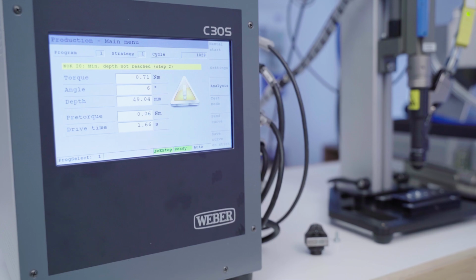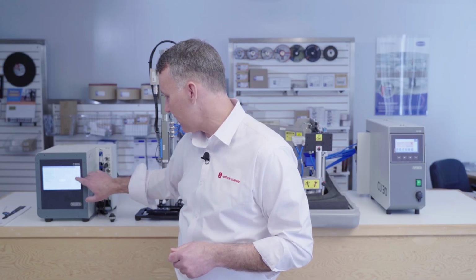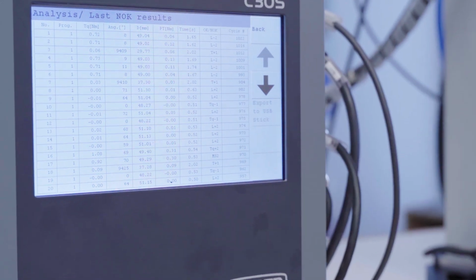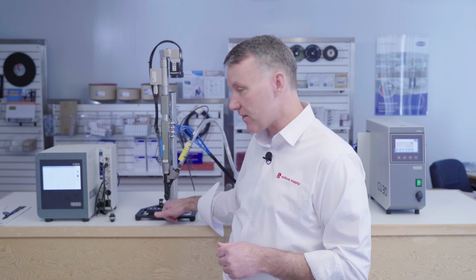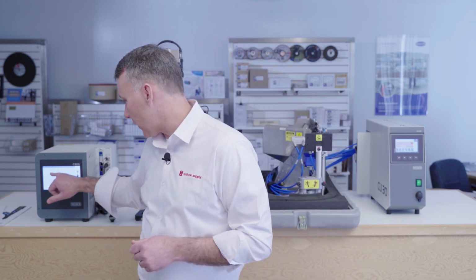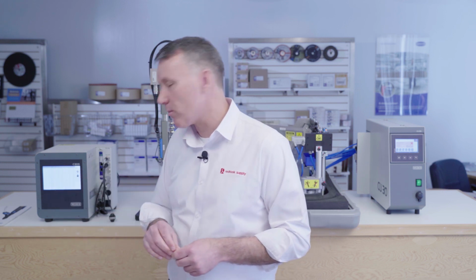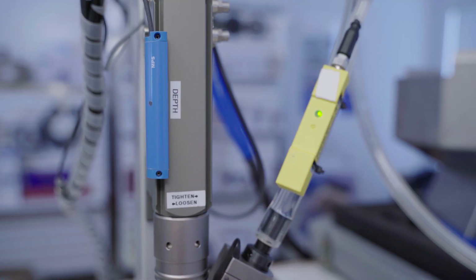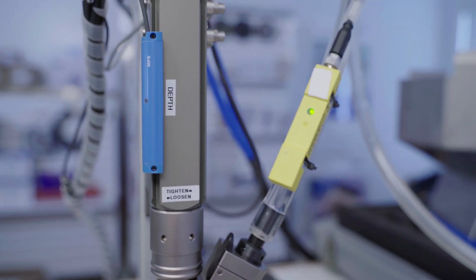So we've got a not okay. If I go to my analysis screen and look at my last results, I failed on depth. But if you look at the difference in torque, the preceding one was 0.8 newton meters and this one was 0.71 — a marginal difference in torque that would have passed all the other systems. However, we were able to detect it by utilizing our analog depth sensor.